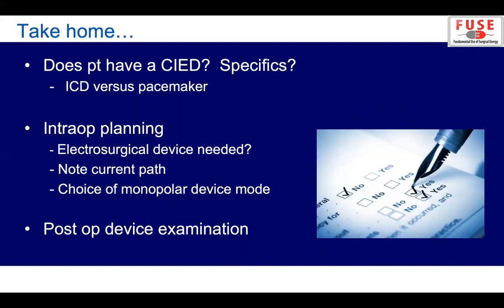So the take-home messages here, again: does the patient have a CIED? If so, what are the specifics? Make sure you understand whether it's an ICD versus a pacemaker or both. For intra-op planning, do you absolutely need that monopolar electrosurgical device? Note where you feel the current path is going to travel and avoid having that travel across the device. And think about your choice of monopolar mode. So use the lowest energy possible, use a cut mode if possible. And post-op, plan to interrogate the device if at all possible.